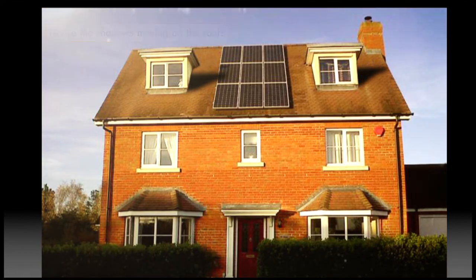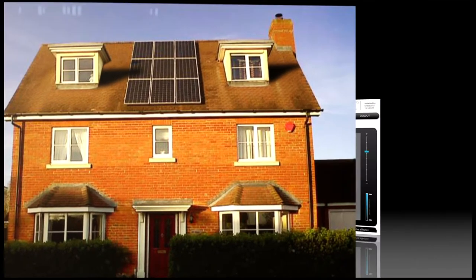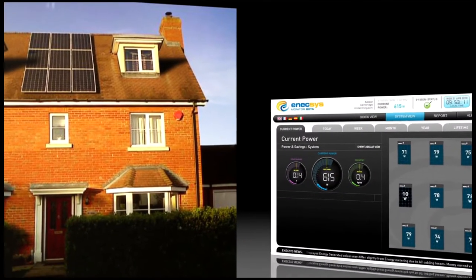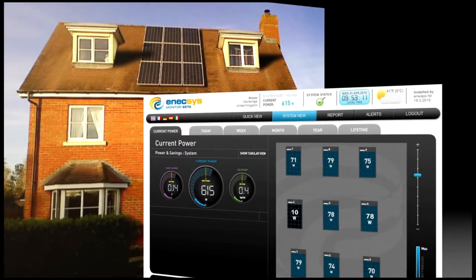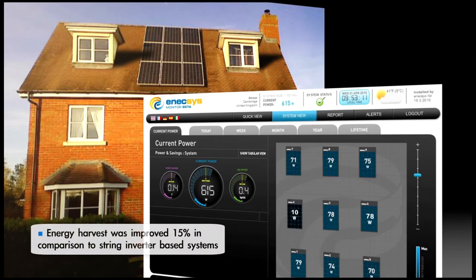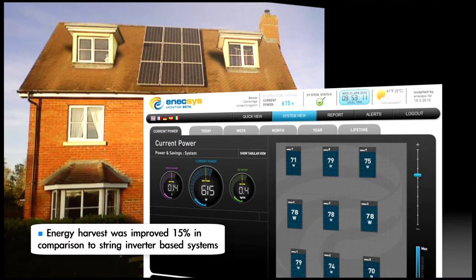If these solar modules were connected in series through a string inverter, this would result in a significant reduction in performance of the entire PV system. However, with the Enecsys microinverter installed at the back of each solar module connected in parallel, the negative impact of these shadows is limited only to the shaded module, maximizing the energy harvest.